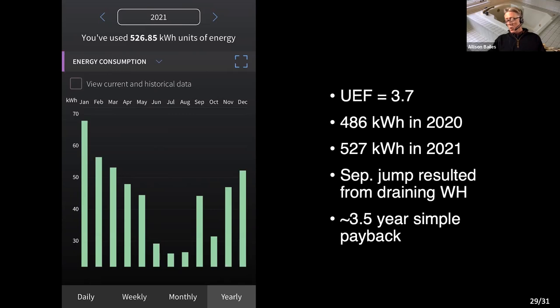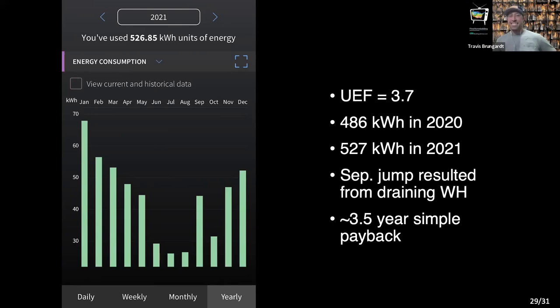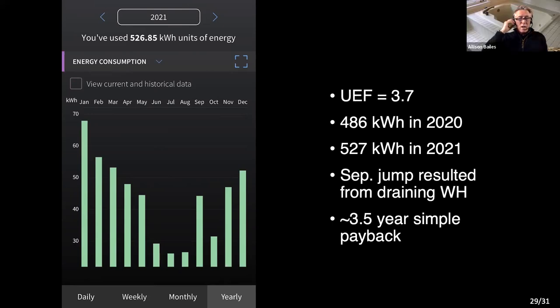The split system heat pump water heater is a great solution for cold climates, because just like with a heat pump for space heating, you're getting heat from the outdoor air, not from inside the house. So you're not robbing Peter to pay Paul—you're getting it from outdoors, making the outdoors colder and getting that heat into the house. It's a good way to go in cold climates if you don't want to use your space heating to keep the air warm enough for the heat pump water heater. They are pricey, though—significantly more than the regular heat pump water heater.